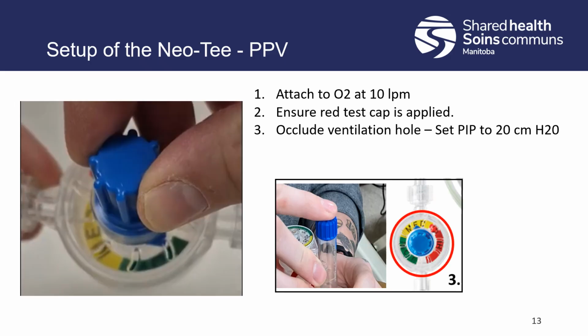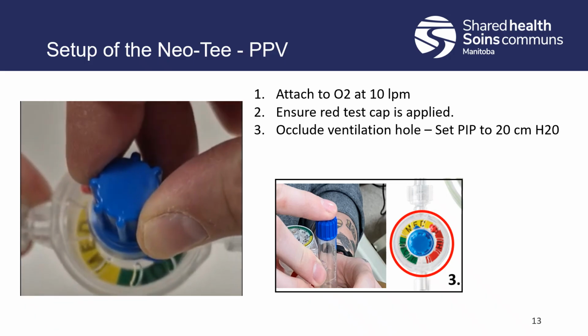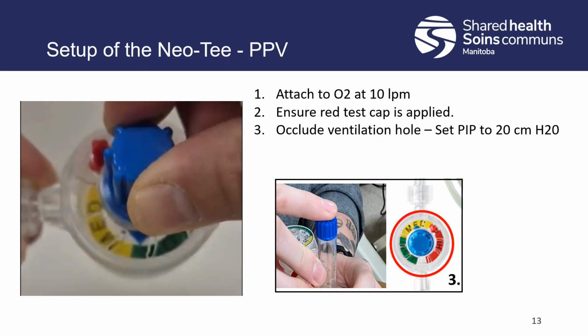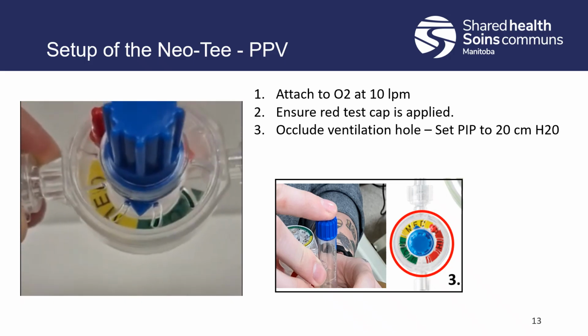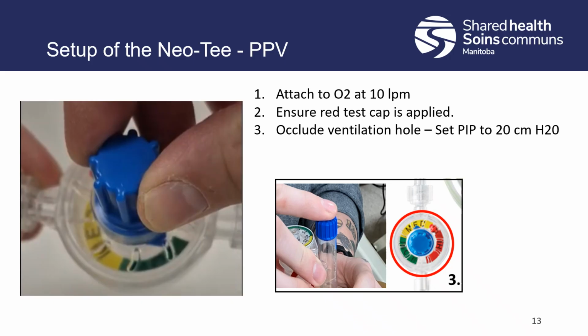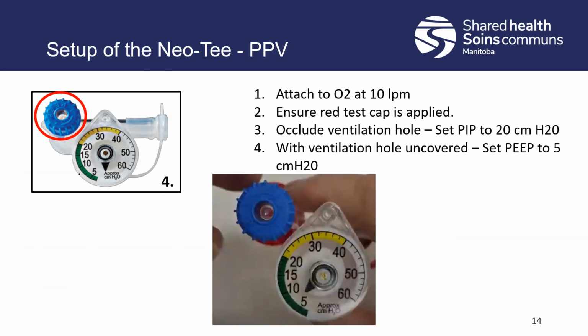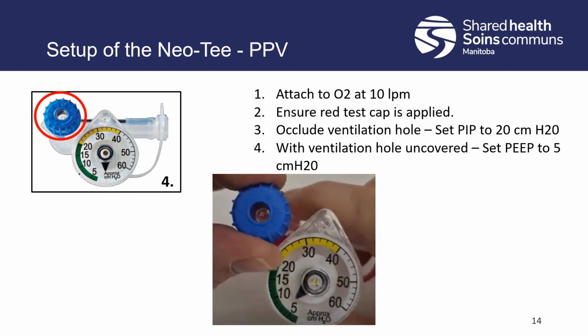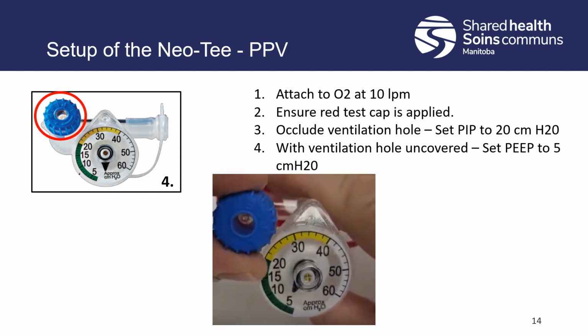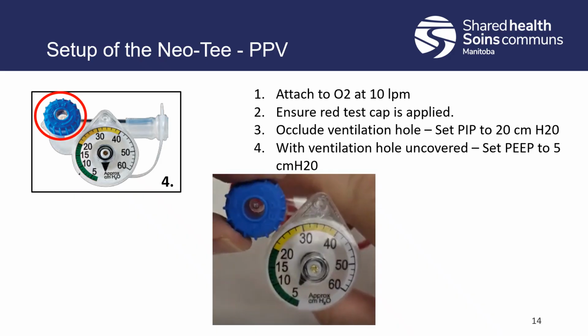So once we've got that applied, if it's not already attached, we're going to occlude the ventilation hole and set PIP to 20 centimeters of pressure. So again, as I said before, you're going to rotate this. You see a little bit of blue part goes in between the green and the yellow. And when we cover the hole on top of the PEEP adjuster there, that should be how much pressure is being put into our baby. Okay. So as you can see here, I'm going to adjust my PEEP. I'm going to rotate that dial to set it to 5.